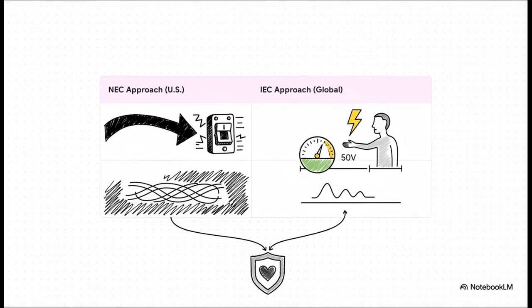It's fascinating to see how engineers around the world tackle this. There are basically two big philosophies. In the US, you've got the NEC approach: their idea is basically brute force, create a super low resistance path so when a fault happens a massive amount of current flows and the breaker trips instantly. Then you have the global IEC approach, which is a bit more elegant maybe; their goal is to just make sure the touch voltage never gets above a safe level, like 50 volts. It's like one is using a sledgehammer and the other a scalpel, but both are aiming for the exact same thing: keeping people safe.